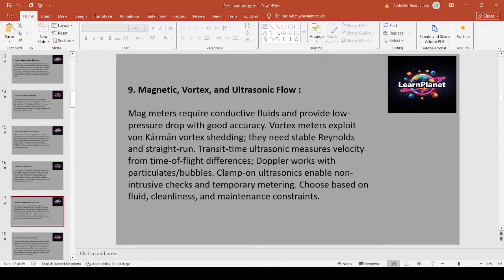Magnetic, vortex, and ultrasonic flow. Magmeters require conductive fluids and provide low pressure drop with good accuracy. Vortex meters exploit von Karman vortex shedding. They need stable Reynolds and straight run. Transit time ultrasonic measures velocity from time of flight differences. Doppler works with particulates or bubbles. Clamp-on ultrasonics enable non-intrusive checks and temporary metering. Choose based on fluid cleanliness and maintenance constraints.